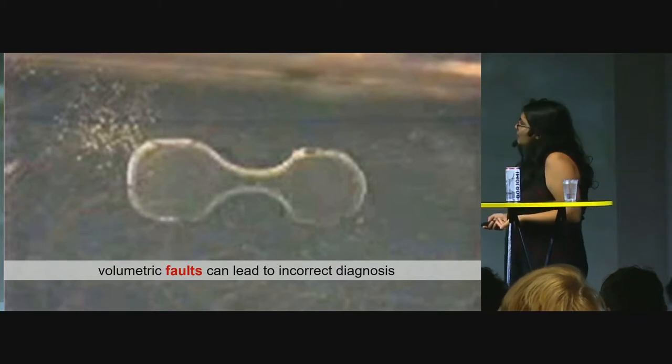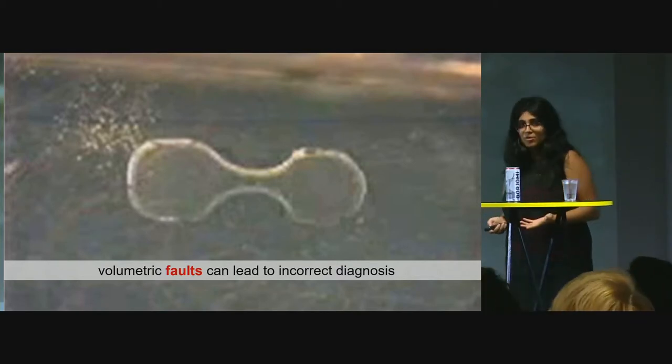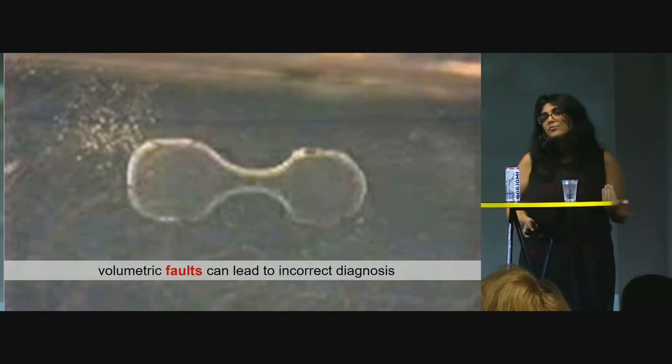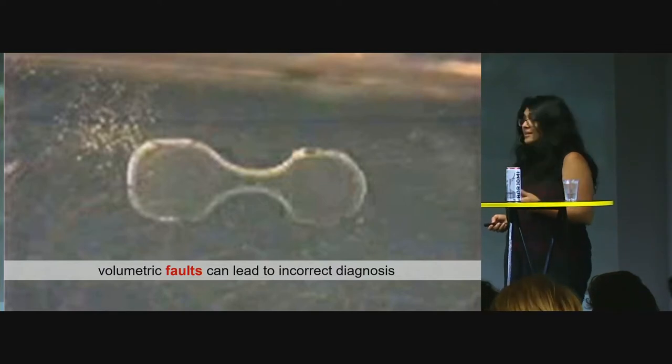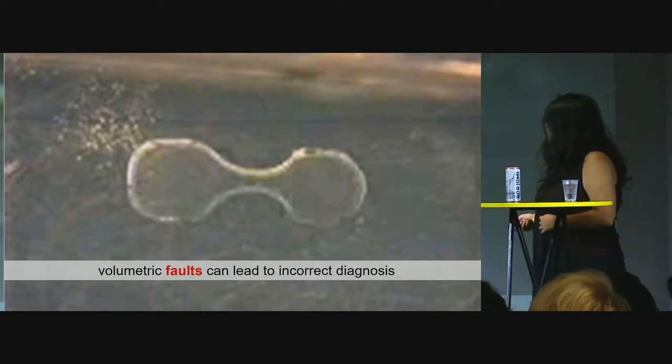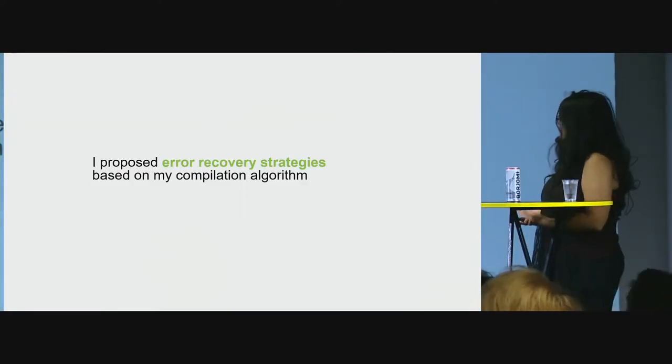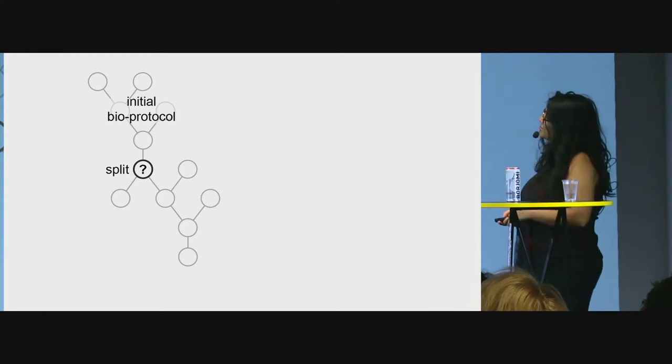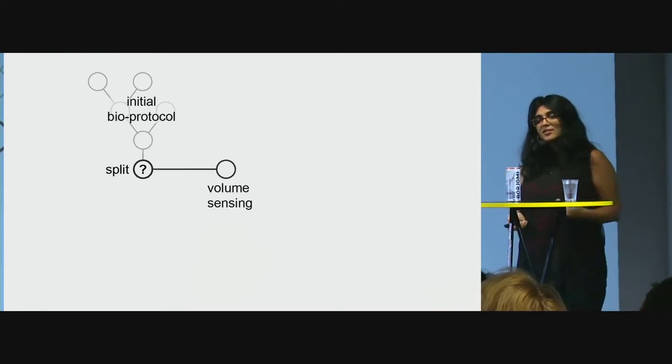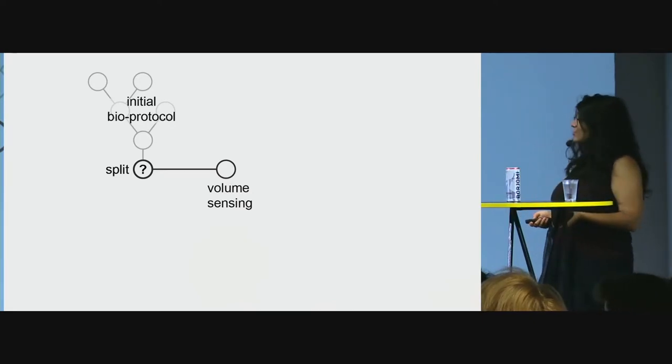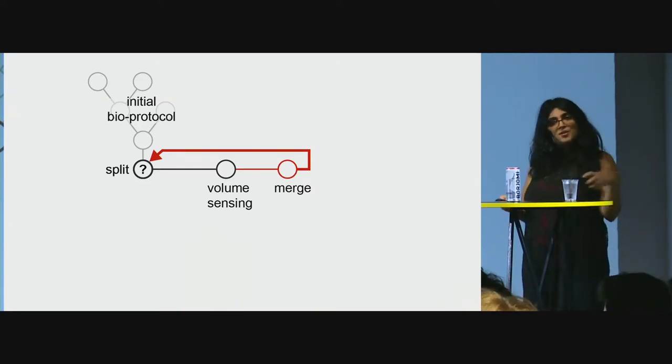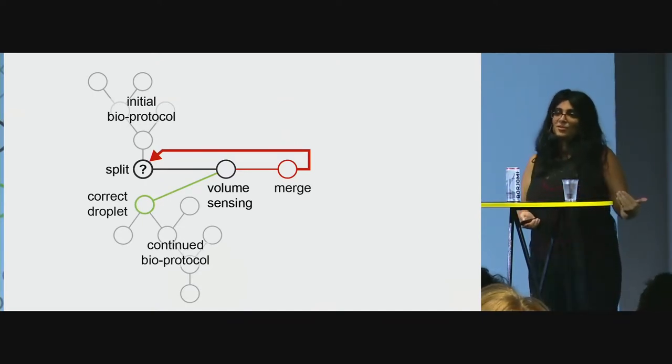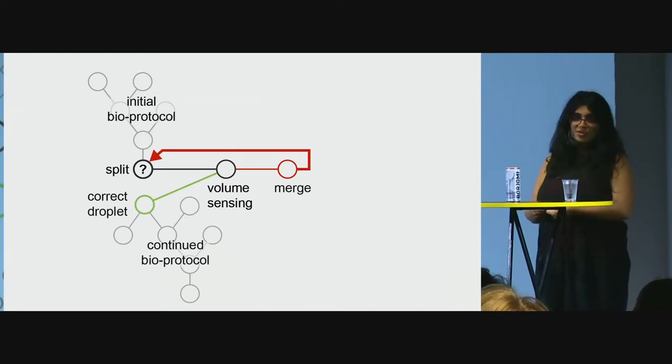So one of the most common fault reasons is the split operation. What you see here is a split that results in two unequal daughter droplets. And unequal volumes lead to unequal concentrations and eventually lead to incorrect results. So you want to solve it as soon as possible. I propose error recovery strategies that are based on my fast compilation. So looking at the split operation, whenever I have a split operation in my graph, I adjust the graph and I insert a sensing operation that takes the droplet to a sensor to check the volume. In case I have an error, I merge the droplet again and then I split them again. And if I don't have an error, I just continue. It's pretty much like restarting your computer. So if we have a split that's erroneous, we just merge them again and we split them again.